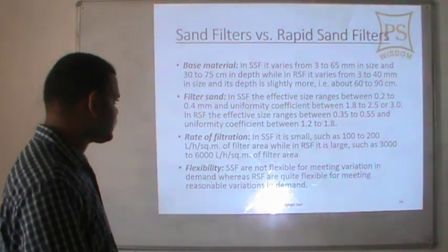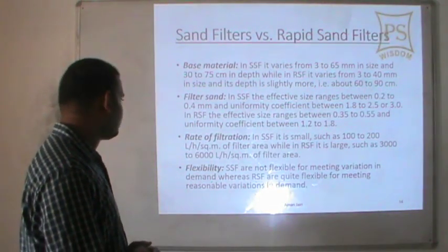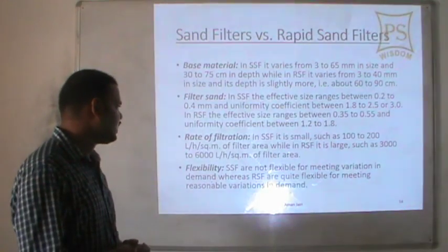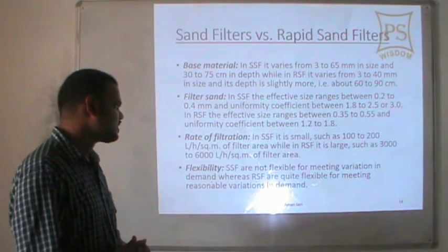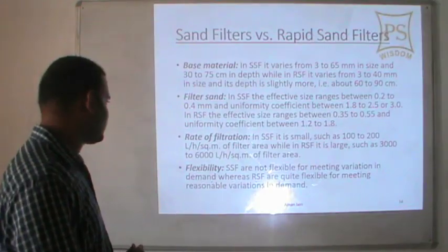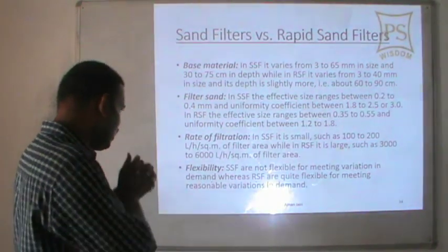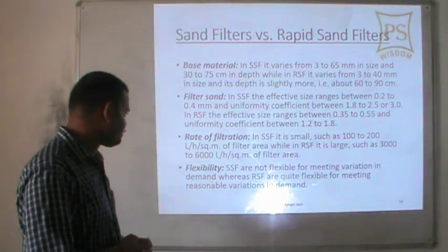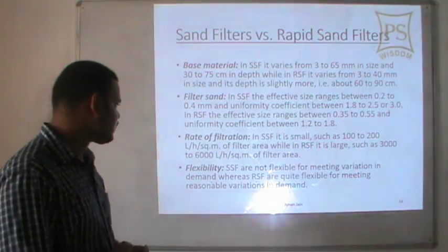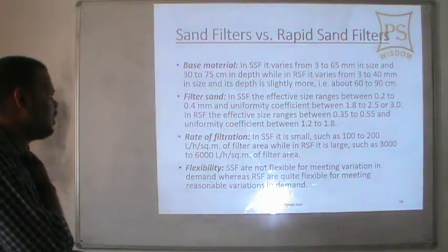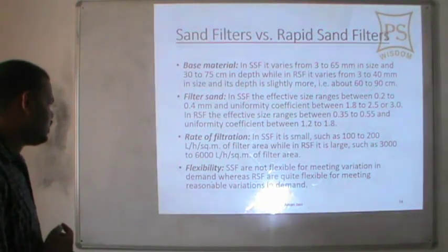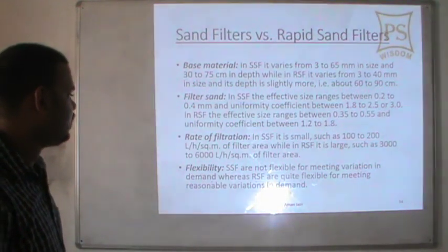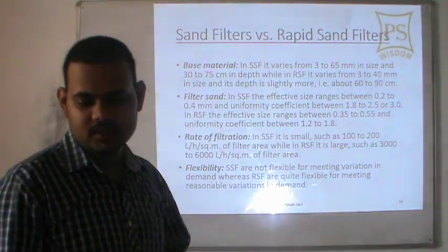Rate of filtration: in SSF it is small — 100 to 200 liters per hour per square meter of filter area; in RSF it is large — 3000 to 6000 liters per hour per square meter. Flexibility: SSF is not flexible for meeting variation in demand, whereas RSF is quite flexible for meeting reasonable variations in demand.